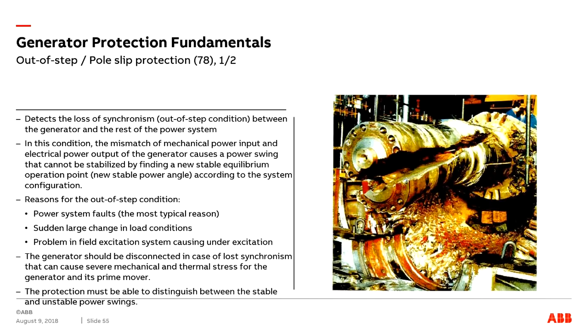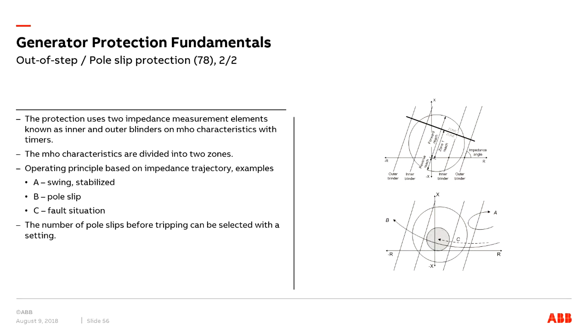So for that purpose, we use a characteristic like this. This protection uses two impedance measurement elements known as the inner and the outer blinders, as you can see here, on the Mho characteristics with the timers. The Mho characteristic is divided into two zones.